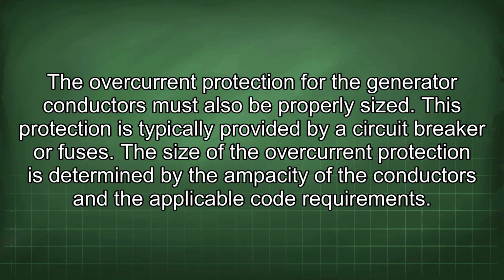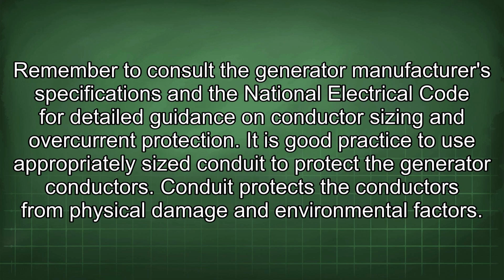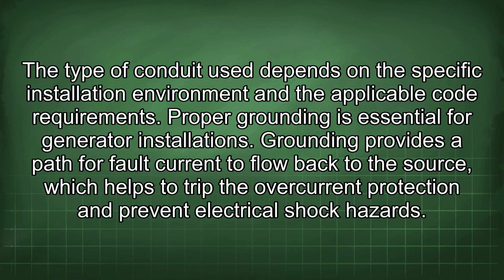The overcurrent protection for the generator conductors must also be properly sized. This protection is typically provided by a circuit breaker or fuses. The size of the overcurrent protection is determined by the ampacity of the conductors and the applicable code requirements. Remember to consult the generator manufacturer's specifications and the National Electrical Code for detailed guidance on conductor sizing and overcurrent protection. It is good practice to use appropriately sized conduit to protect the generator conductors. Conduit protects the conductors from physical damage and environmental factors. The type of conduit used depends on the specific installation environment and the applicable code requirements.